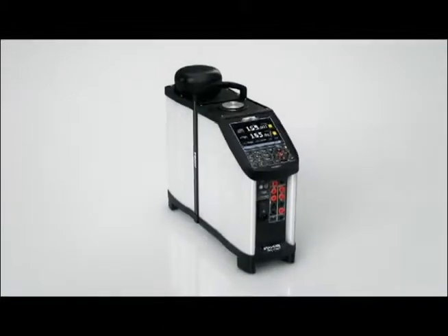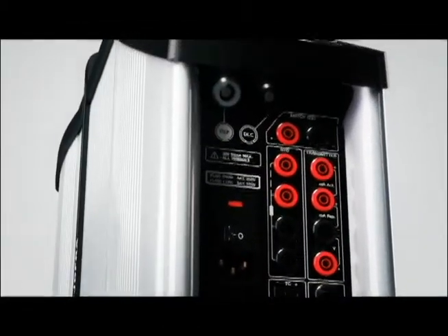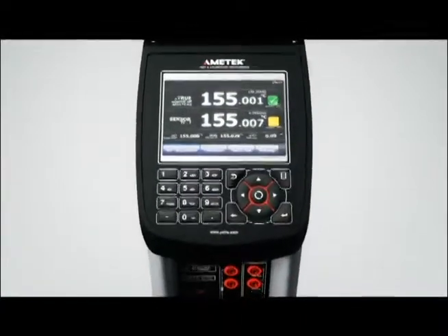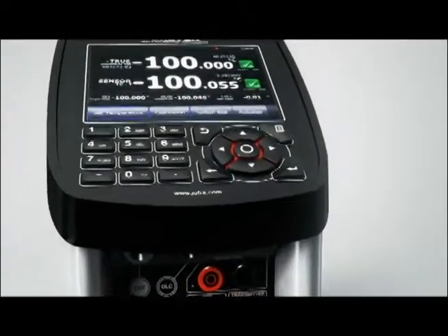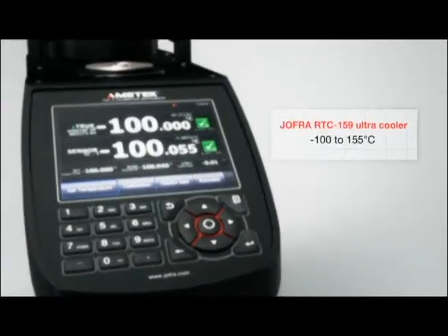AMETEK Test and Calibration Instruments introduces the JOFRA RTC-159 Reference Temperature Calibrator. Thanks to AMETEK's well-proven, patent-pending solution based on Stirling technology, the RTC159 is the only dry block with a temperature range from minus 100 to plus 155 degrees Celsius. You can meet all of your temperature calibration needs in this one unique unit.